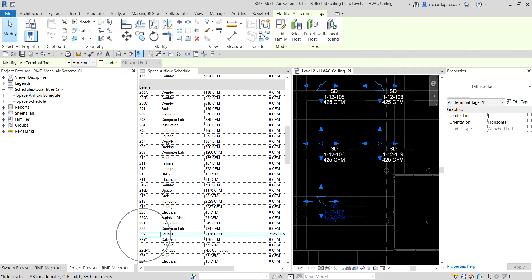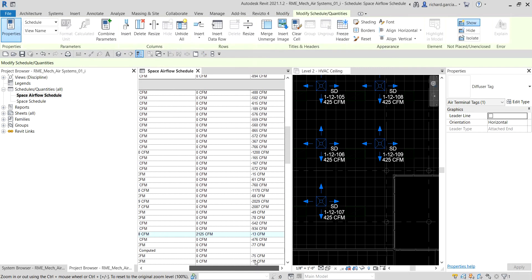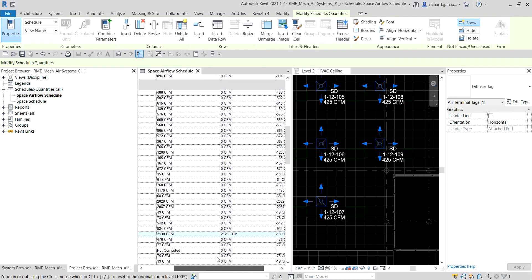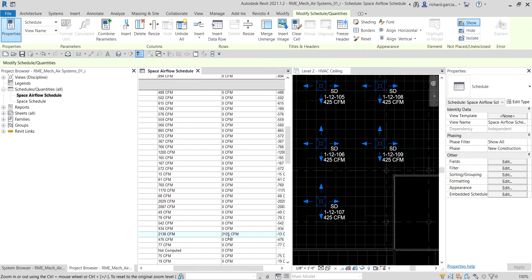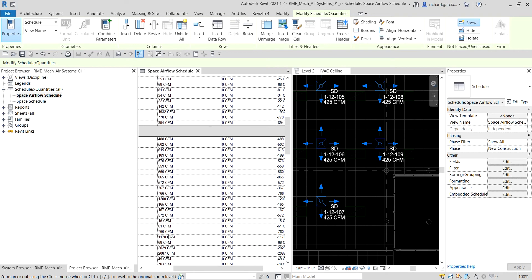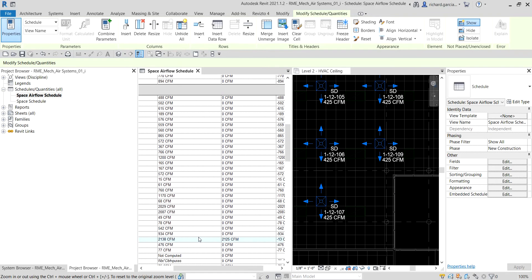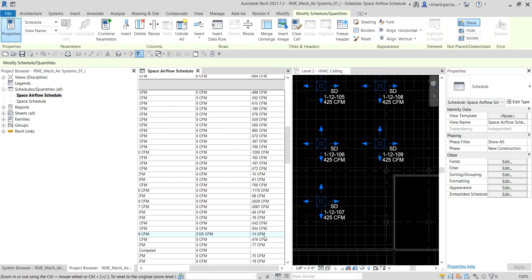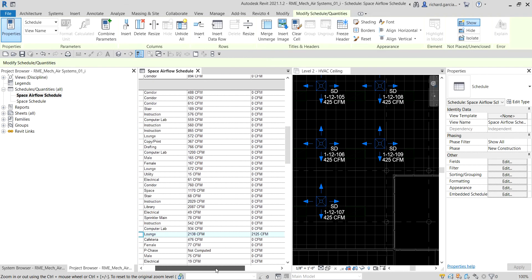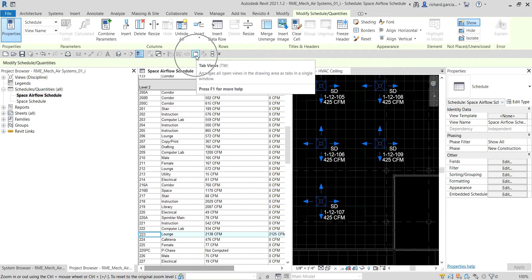There you go — we can now see the tags on room 223. The calculated supply airflow for room 223 is 2,138 CFM and our actual supply airflow is 2,125 CFM — very close. The airflow delta value is within the acceptable range.